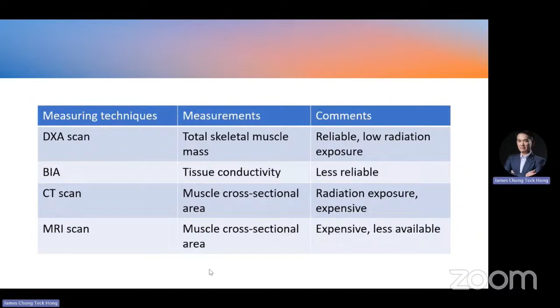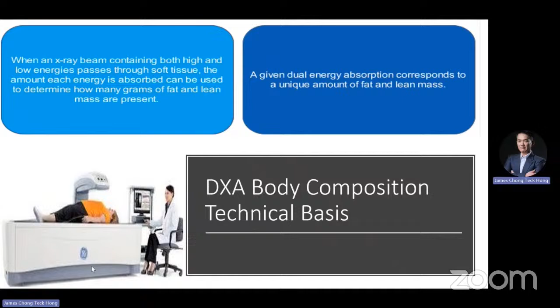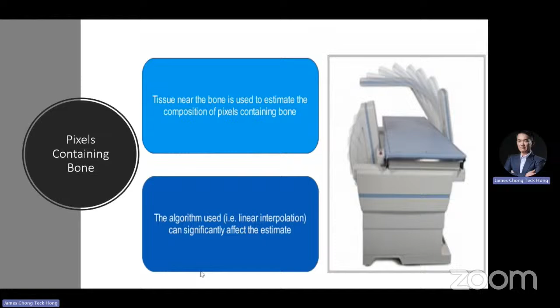So what is DEXA? A DEXA scanner captures dual energy attenuation data for every pixel in the image. To ensure accuracy, it uses a calibration standard usually made of plastic, which is scanned using the dual energy X-ray beam. Plastic and soft tissue both absorb X-rays similarly, allowing plastic to serve as a standard for fat and lean tissue in a whole body phantom. By comparing the X-ray attenuation from each image point to the calibration curves obtained from measurement of these standards, the scanner calculates the fat and lean mass for each point in the image. As mentioned earlier, one limitation of DEXA is the inability to directly measure the soft tissue composition within pixels containing bone. While it can measure total tissue mass, it relies on estimating the lean and fat components from surrounding tissue points.